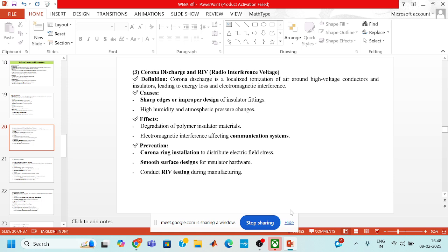Now, third is corona discharge and RIV, which is known as radio interference voltage. Corona discharge is a localized ionization of air around high voltage conductors and insulators, leading to energy loss and electromagnetic interference. Sharp edges or improper design of insulator fittings, high humidity, and atmospheric pressure changes can all cause corona discharge. Due to corona discharge, there is degradation of polymer insulator materials, and electromagnetic interference also occurs, which can affect communication systems. To prevent this, we use corona ring installation to distribute the electrical field stress equally, we can use smooth surface design for insulator hardware, and also conduct RIV testing during the manufacturing process.